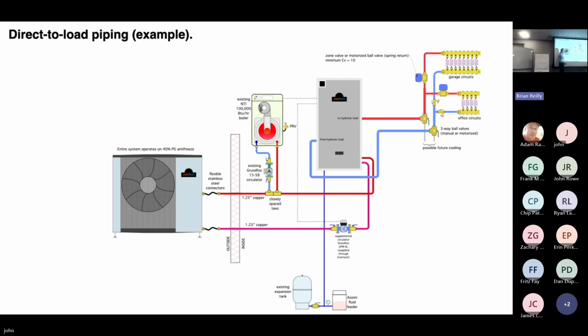So what Enertech sells is a monoblock heat pump with this indoor box, and the installer basically just connects piping between the indoor box and the outdoor unit. They tap the boiler in with a pair of closely spaced T's. Again, this would have flow going through it whenever the load is active. And I've shown this supplemental circulator. There are cases where this might be required, but cover that up for the time being.